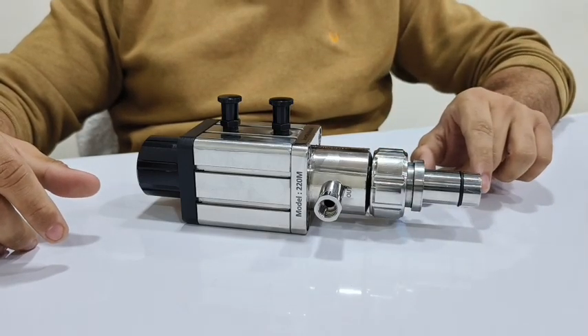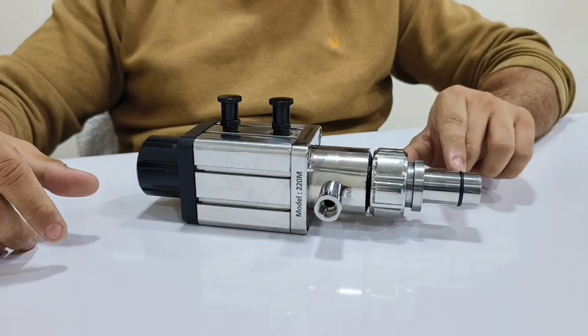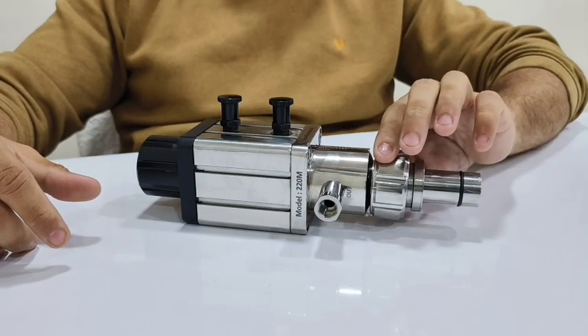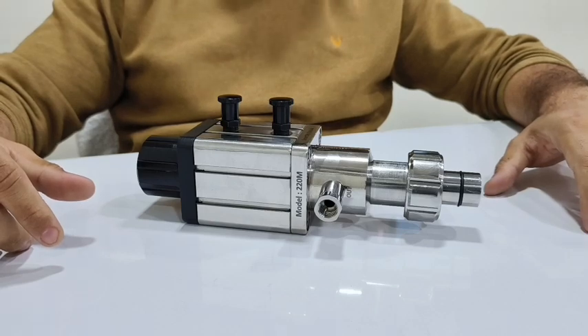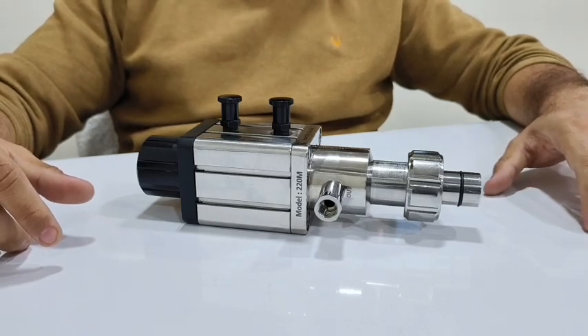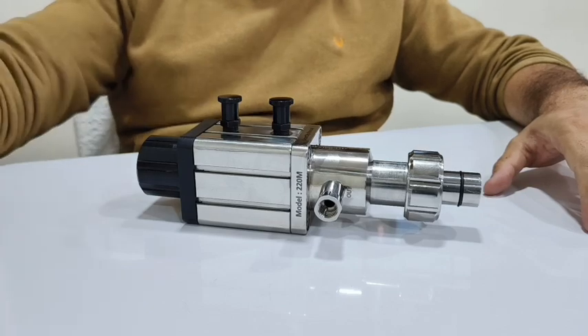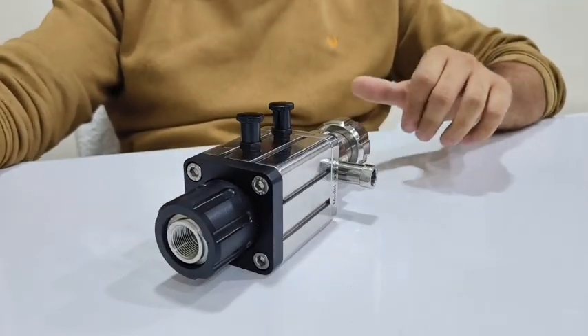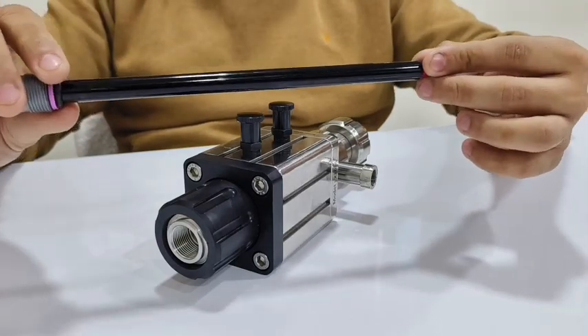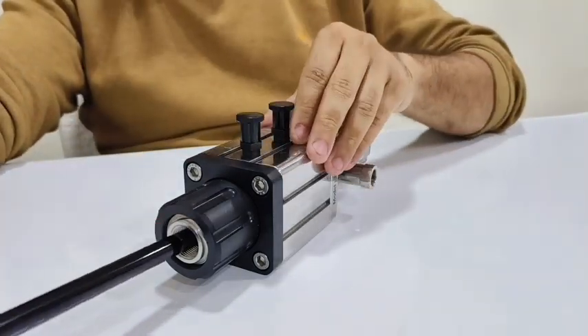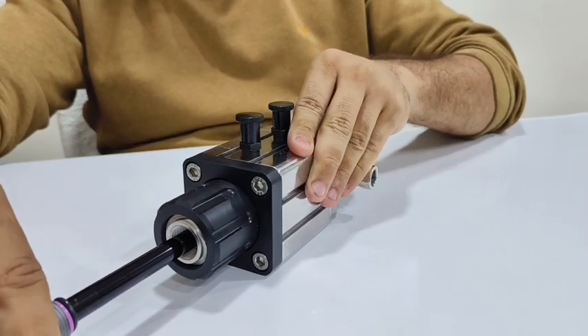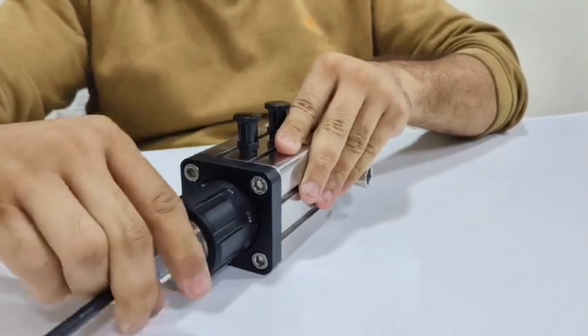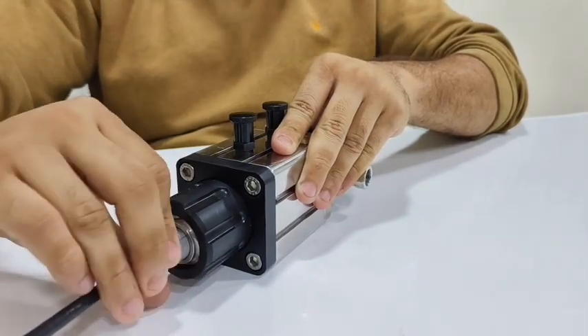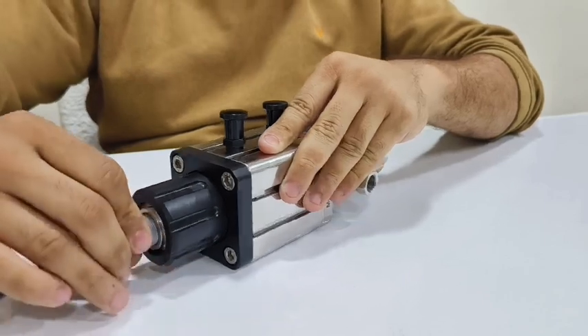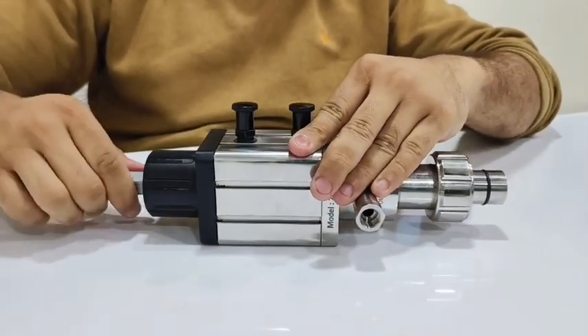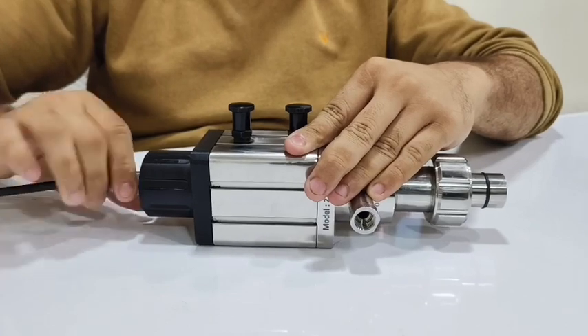The immersion length from the collar is 40 mm and the O-ring position is 25 mm from the collar. Let me show you how the pH electrode can be implemented inside of the retractable electrode housing and its operation. This is a 225 mm long pH electrode with 12 mm dia. We can insert the pH electrode from the top of the retractable electrode housing. Any pH and DO sensor with standard PG 13.5 thread can be implemented in the retractable electrode housing.